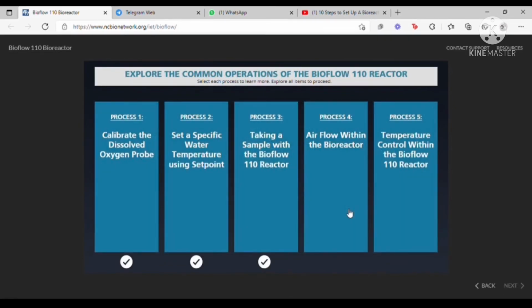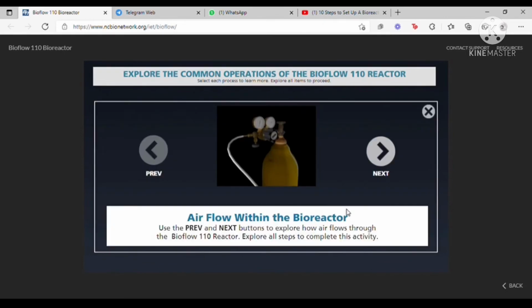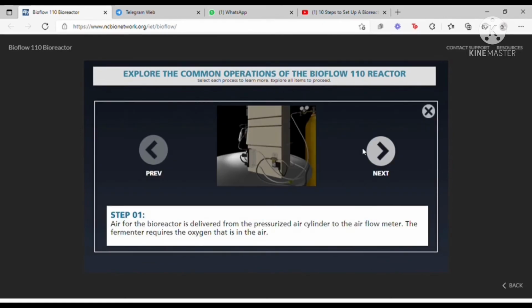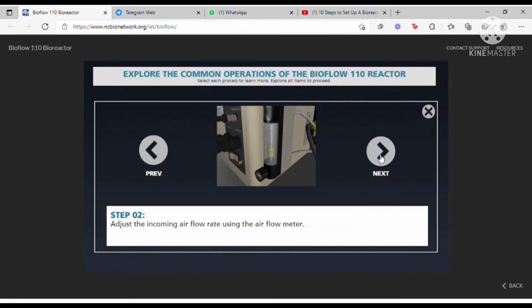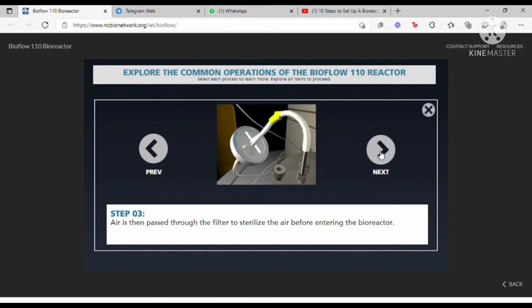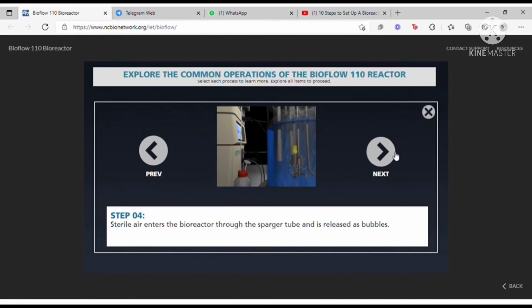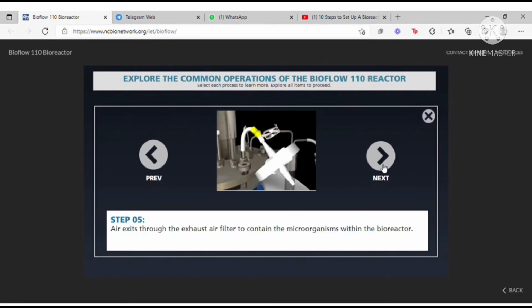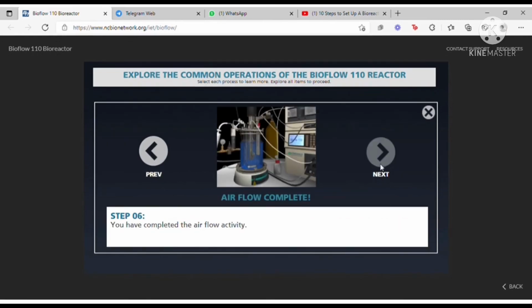The next process would be the airflow within the bioreactor. Step 1 would be air for the bioreactor is delivered from the pressurized air cylinder to the airflow meter. The fermenter requires the oxygen that is in the air. Step 2 would be to adjust the incoming airflow rate using the airflow meter. Step 3 would be air is then passed through the filter to sterilize the air before entering the bioreactor. Step 4 would be the sterile air enters the bioreactor through the sparger tube and is released as bubbles. Step 5. Air exits through the exhaust air filter to contain the microorganisms within the bioreactor. The airflow activity is now complete.